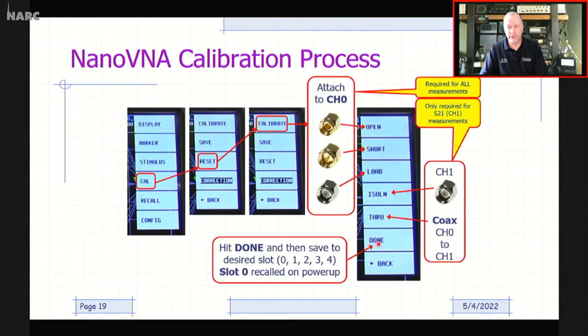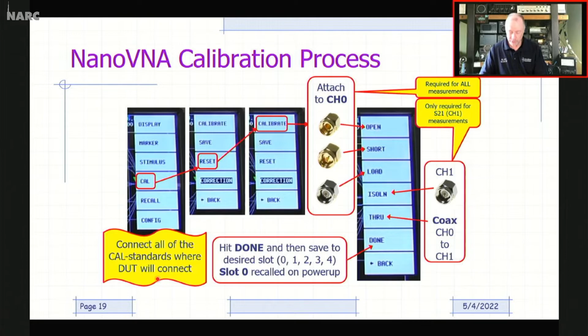Okay. One thing important to remember is that whatever calibration is stored in slot number 0 gets recalled when you power up the device. So that's kind of your default calibration, whatever is stored in slot 0. And ideally, you'd want to connect all of these cal standards to where your device connects. And that's, as I mentioned before, to establish that measurement plane at your device interconnect point. Okay. Now, sometimes that's just not possible. Okay. And if it's not possible, one thing you can do is do something called a port extension.